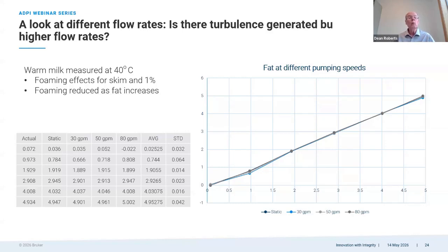Here we looked at the warm milk measured at 40 degrees C. We still see the impact of what we think is the foaming at the skim and at the 1%, but the other ones line up perfectly with the predicted versus actual with no slope and offset correction. When we look at the different flow rates, we see that the 80 gallon per minute is quite a bit off from the actual value, and we're reading a little bit lower on those.